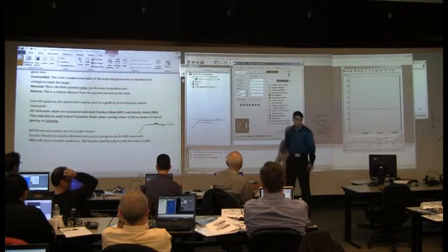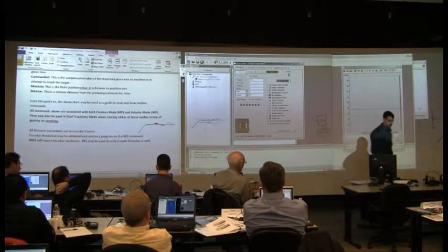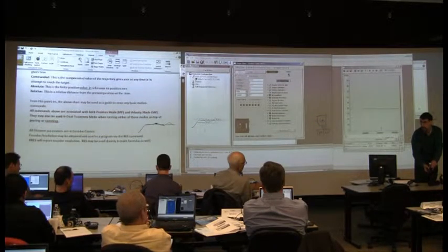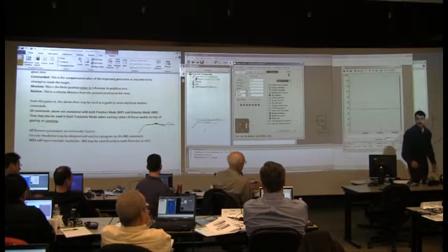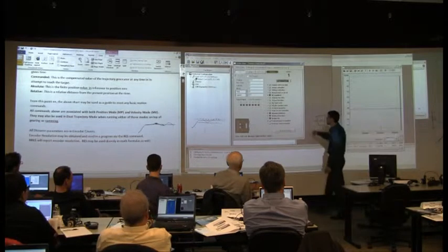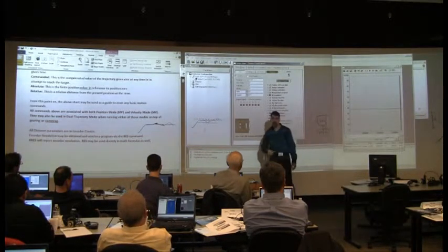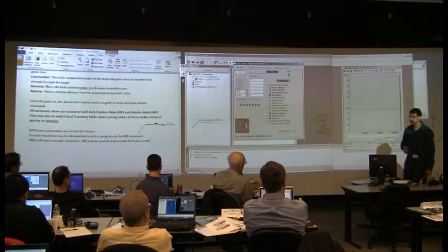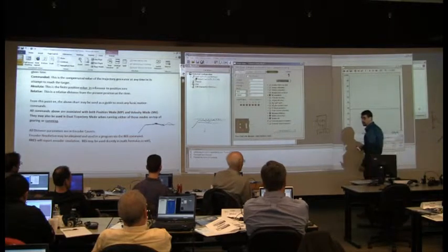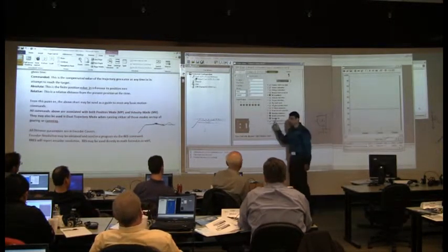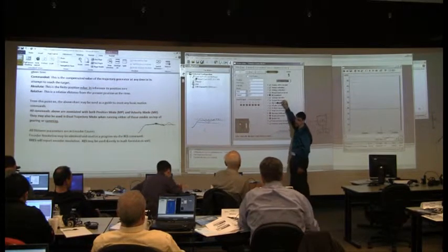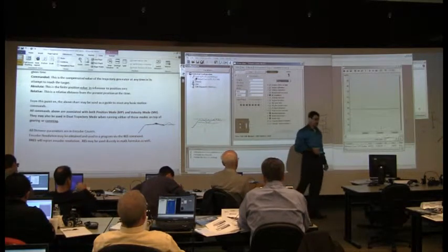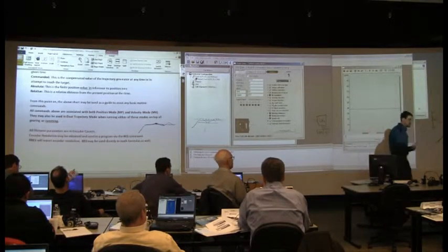I/O fault latch, that's the expanded I/O connector on the back of the motor. Okay? This expanded I/O connector does have overcurrent and thermal shutdown. If you get an I/O fault latch, the only way to clear it is to power down and reset that chipset. Not the whole motor, but just the external I/O. It is the only way to clear that. Okay, I'm going to repeat it again. The only way to clear an I/O fault latch, which applies to external I/O, is to power down that 12-pin connector and bring it back up.